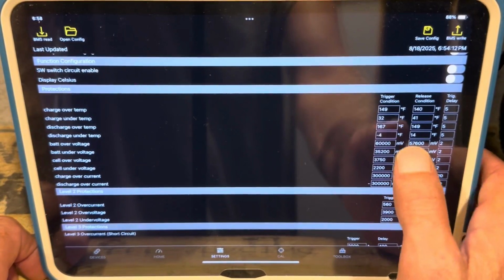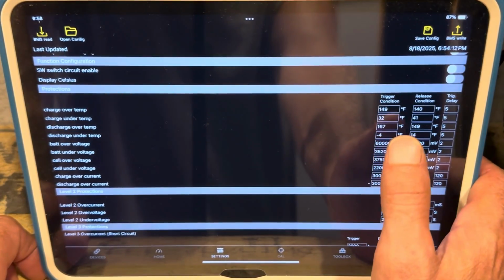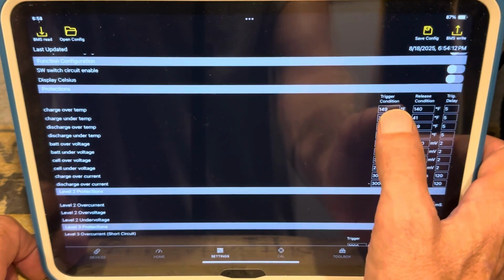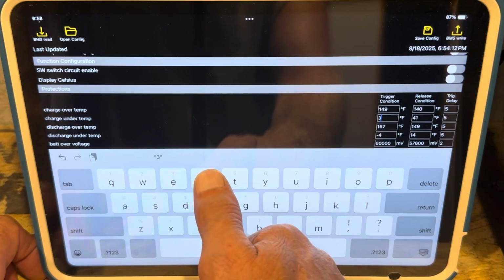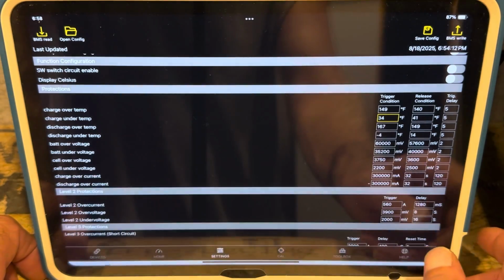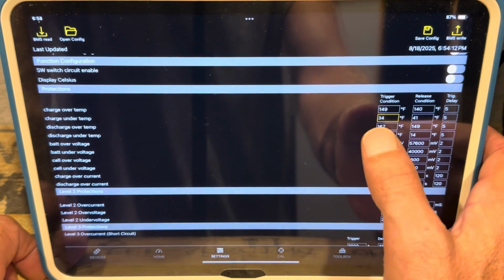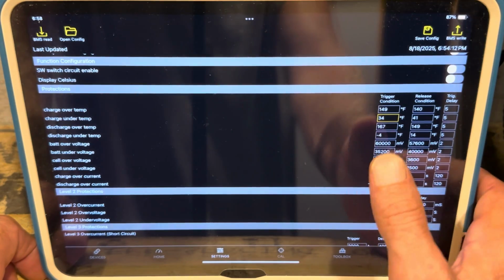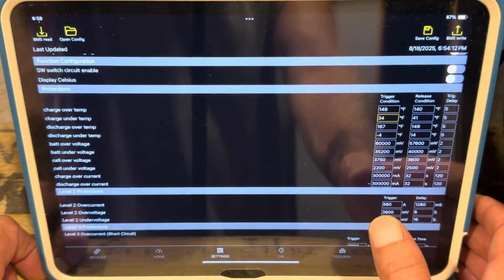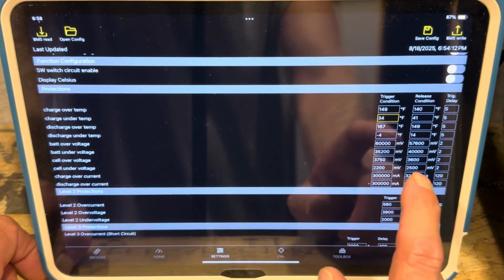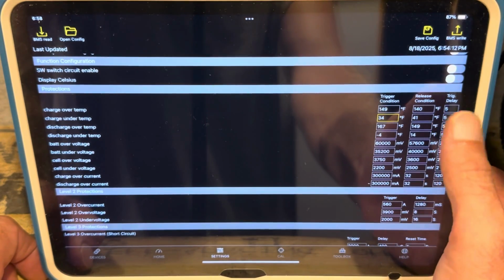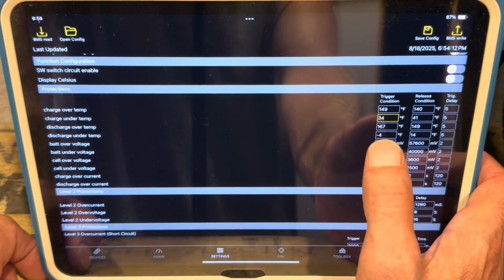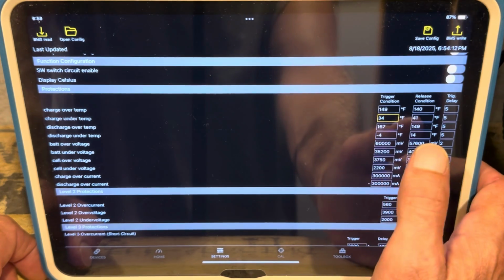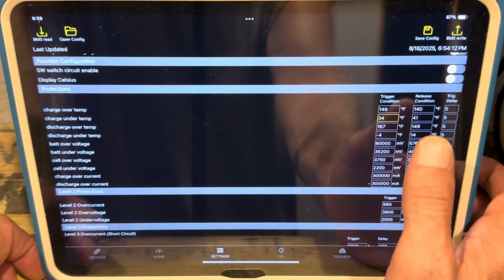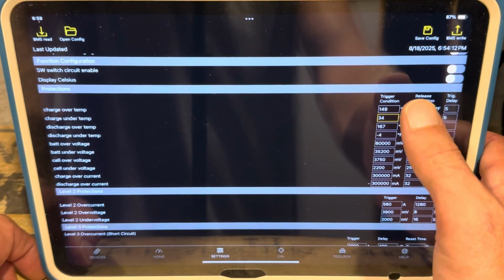They give it a little more range for surges and things like that, but I still don't like my cells going into these voltage thresholds. Another thing I usually do with these batteries: the charge under temp protection is set at 32, but just to err on the side of caution, I usually set it to 34 degrees Fahrenheit. Notice anything I change gets a highlighted box, so you can look back through before you write the program to see what you've changed. I'm okay with the other settings, and the discharge under temp settings will be based on the cell manufacturer's data. Hopefully these are right.